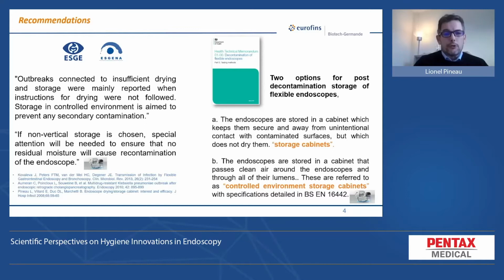In another document published in the UK, the HTM 0106 guideline, published in 2016, two options are provided for endoscope storage. The first one is to use a storage cabinet without drying function, but in that case, you have to dry your endoscope manually before storage. And we know that endoscope drying is something very, very complicated. The other option is to use a drying storage cabinet consistent with the EN standard 16442. And the main characteristic of this process is passing air through all endoscope channels. So two options to avoid recontamination of the channel during storage.